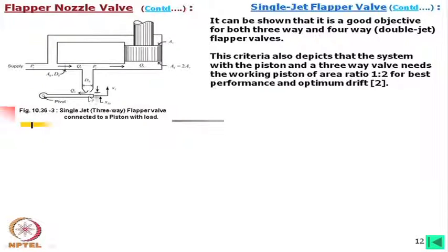You will find that when this piston cylinder is at the central position, it is basically controlling a spool, which should be in such a position that the spool is also in the null position. But due to leakage and error, when this is in the mid position, what it is controlling is not in the null position. So this null position and that null position may not match, and that is called drift. Now there is also a technique by which we can control the drift, okay.